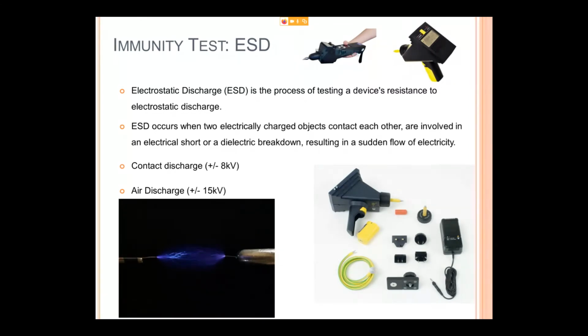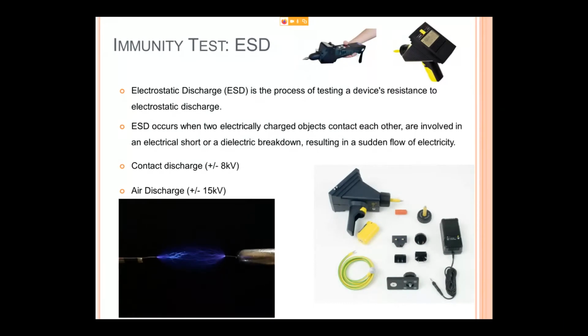So electrostatic discharge testing is the process of testing the device's resistance to electrostatic discharge. The gun which I have shown above, or below, has a pointed conductor tip. If you keep the tip on the EUT, it will emit the electrostatic discharge. You can set, like, 1 pulse per minute or 10 pulses per minute. So you have to test your equipment and get it certified.